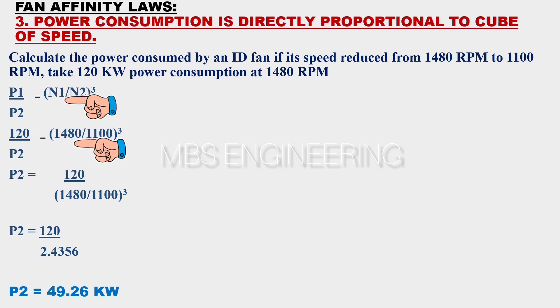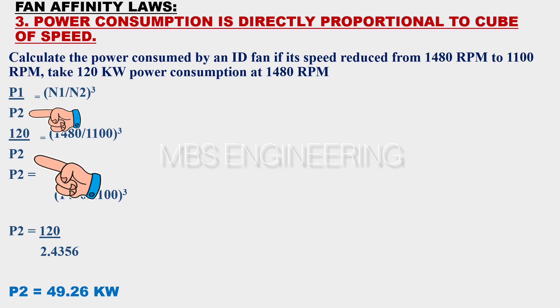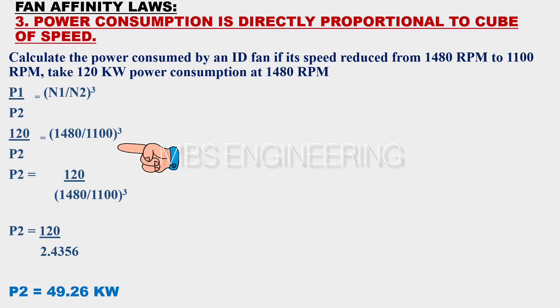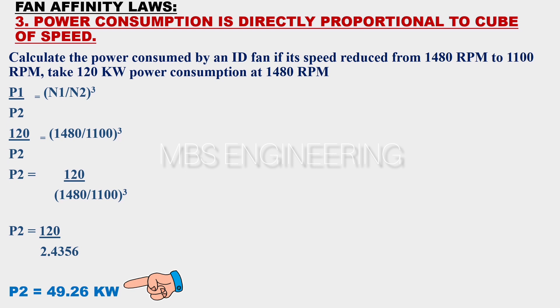Speed N1 is 1480 RPM and speed N2 is 1100 RPM. We need to calculate P2. Then 120 divided by P2 equals the cube of 1480 divided by 1100. Please refer to the below step-by-step calculations. Based on the above equation and given data, the obtained power consumption P2 at a speed of 1100 RPM is equal to 49.26 kilowatts.